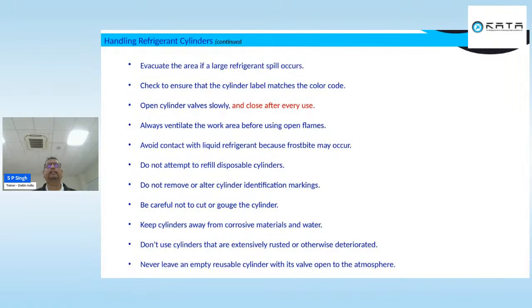So this is in continuation of the handling of refrigerant. We should open the cylinder valve slowly. We should never open it suddenly. We should have a proper valve so that it can rotate gradually, so that the refrigerant is not released immediately.